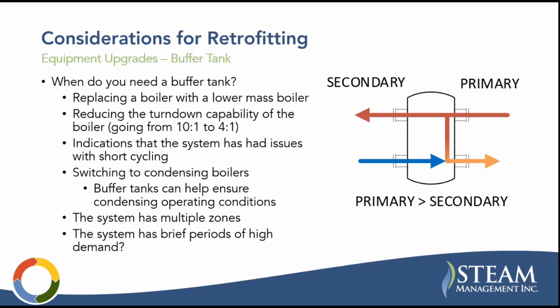That could apply. That's not as big of a point in these condensing boilers because often you're going to have multiple boilers. They generally have advanced controls and high turn down rates, and then your overall turn down is multiplied by the fact that you're turning down to the minimum of one of the three boilers instead of the one large boiler. Anyway, if there are indications that the system has had issues in the past with short cycling, you may need a buffer tank. If you're switching to condensing boilers, you're often reducing the volume of the boiler, so it's something you should pretty much always consider or at least evaluate.